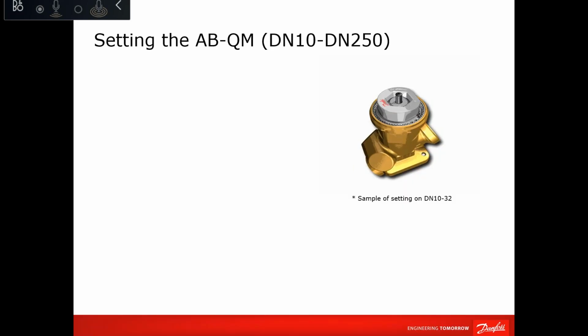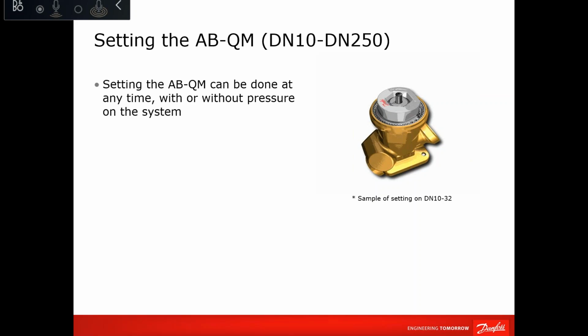So now we spoke about the two-way, the control part of the PICV. We spoke about the differential pressure controller of the PICV. Now we will move to the manual balancing part of the PICV, because yes, we have that as well. So the upper part, on DN10 up to DN32, there is a gray locked mechanism. If you pull it up, you will release the rotating movement, which I was talking about when I was explaining about different types of PICVs.